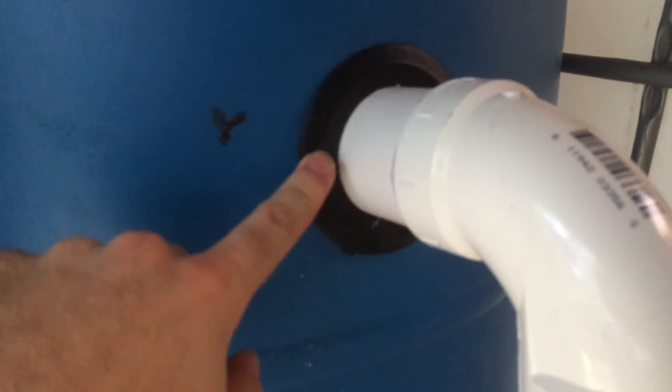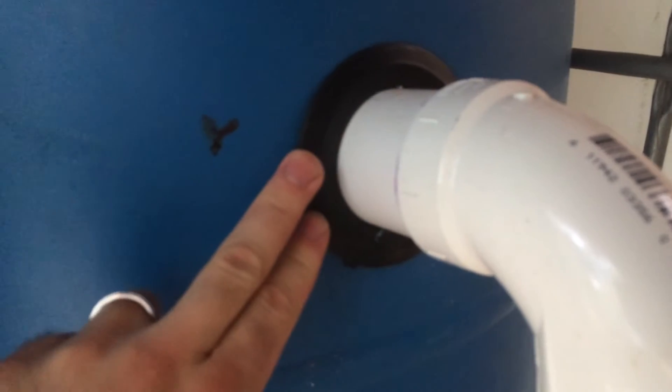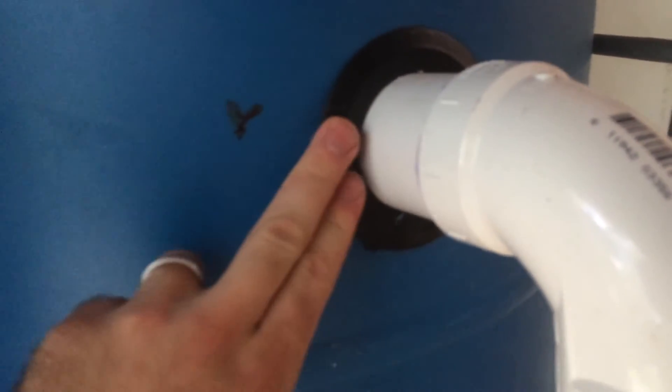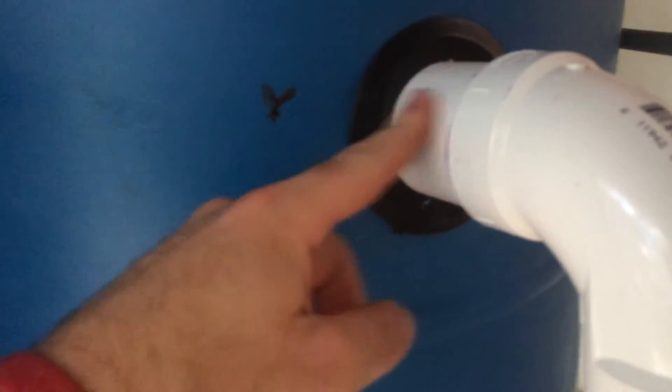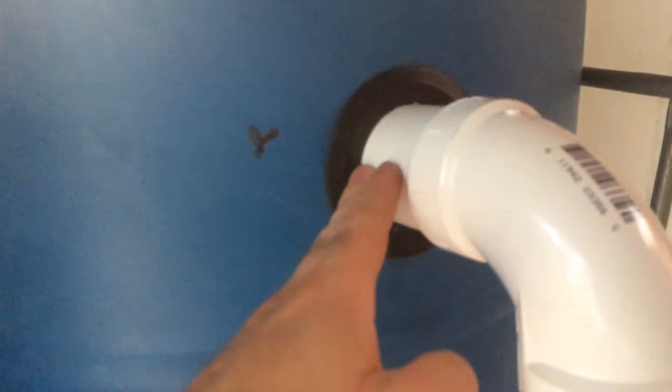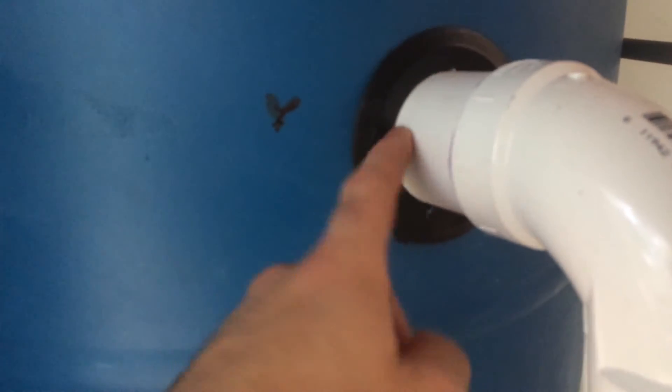When you drill these holes out, the manufacturer's specs tell you exactly how big to drill a hole, which is right. Follow their rules. But on your pipe that you're going to push through, sand the leading edge of it, where the tip of the nipple, so to speak, whatever pipe you're pushing through, where you've cut that sharp edge, sand that, round those corners off, taper as much as you can safely, and that'll help you tremendously on pushing these things through.